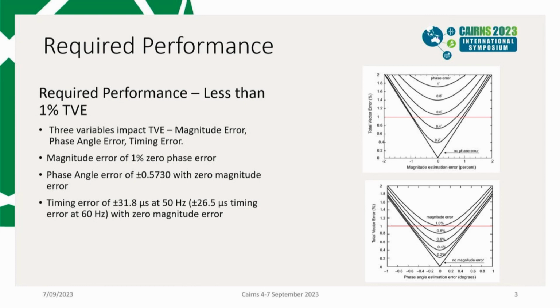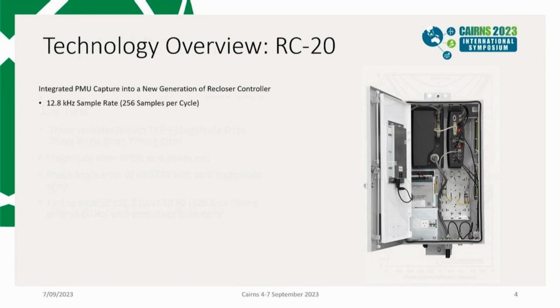Now, the idea was hatched that we could partially use the existing overhead distribution network protection assets to gather this information, specifically pole-mounted auto reclosers. Many pole-mounted auto reclosers that are installed in the field today already have the primary sensors that would be necessary to do this. However, there would have to be an improvement in the technology, the controllers that were attached to those. And so it was decided earlier on that we would enhance the recloser controller to integrate a PMU capture into that new generation of recloser controller.